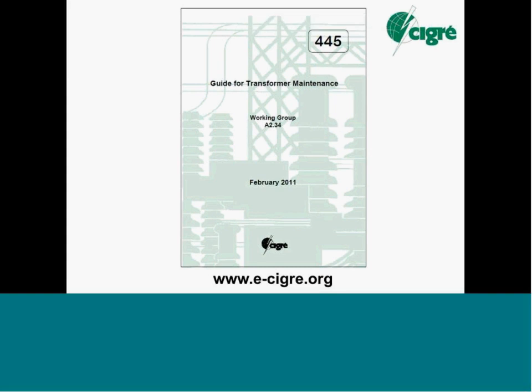If you discern a change in the leakage reactance, single-phase leakage reactance is the test normally done to discern a change in the impedance, and you would do a comparison of A, B, and C phase. If there's been a collapse after a major circuit fault, a major through fault in the transformer, in other words, the transformer has tripped offline, there's been a short circuit fault involved, and you know it's been subjected to very high through current, then electrical tests would include single-phase leakage reactance and FRA, as well as some other electrical tests to decide whether the transformer suffered. An internal inspection is warranted.